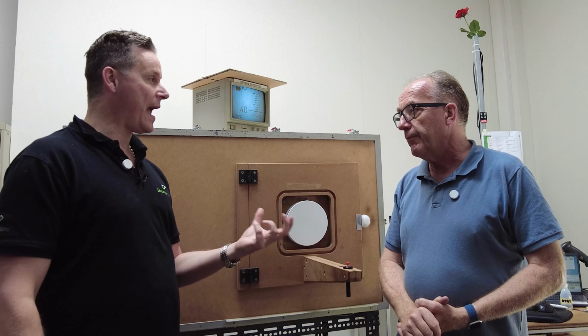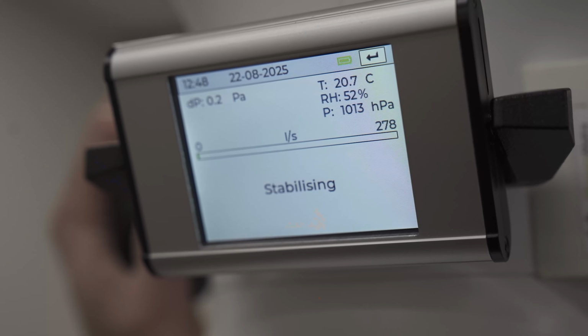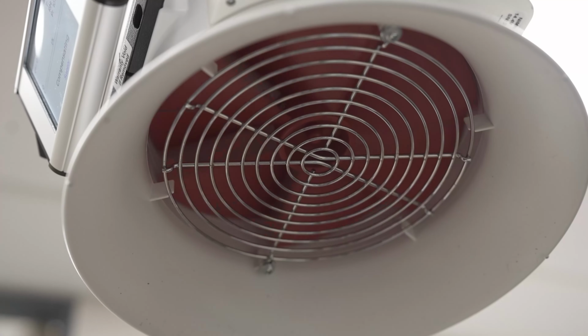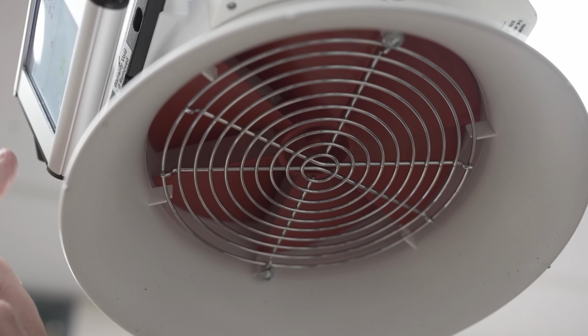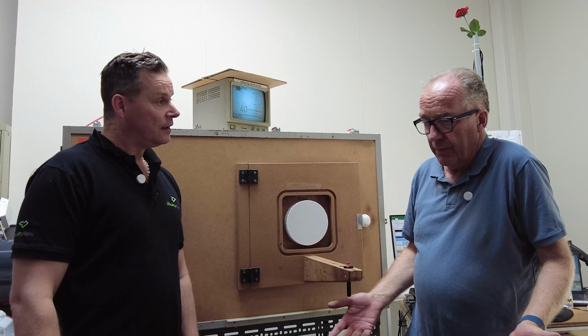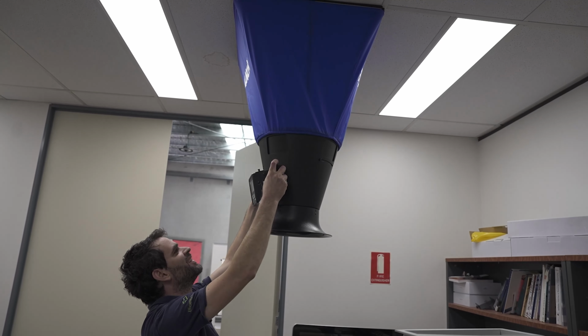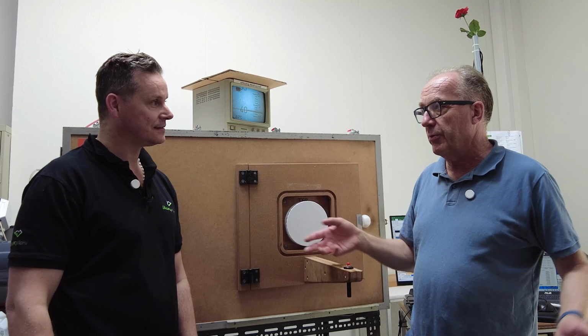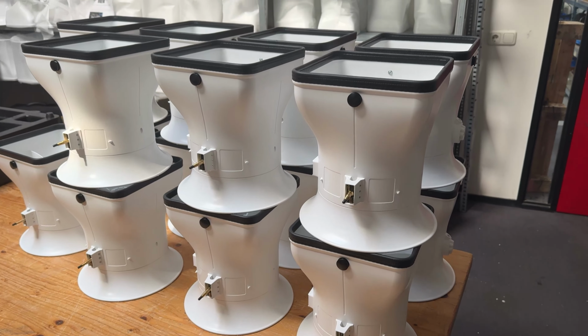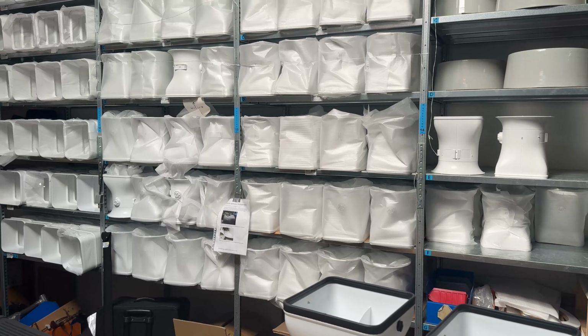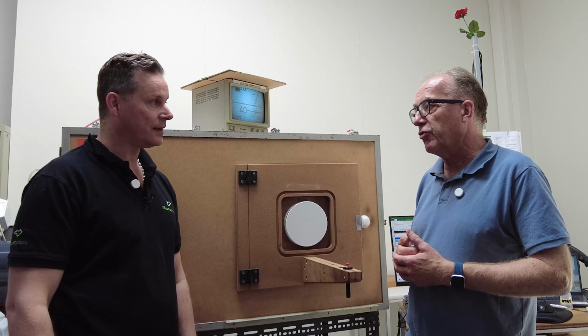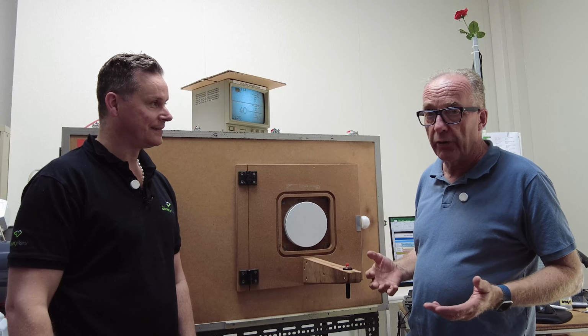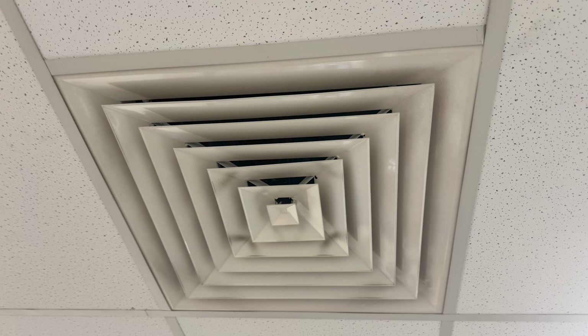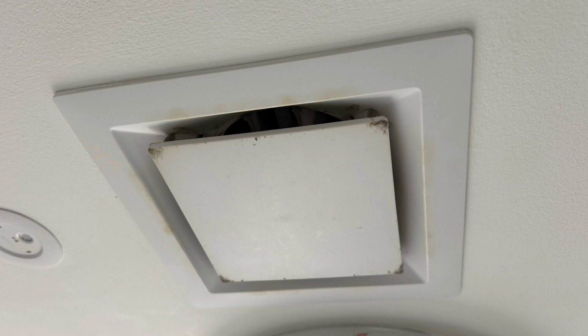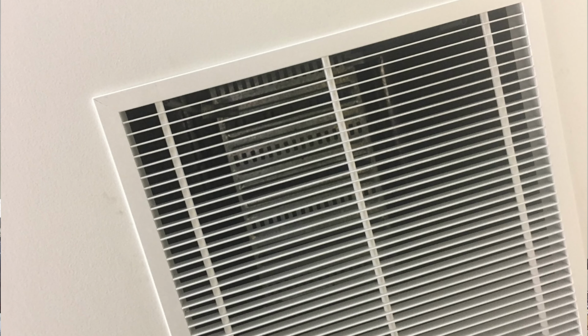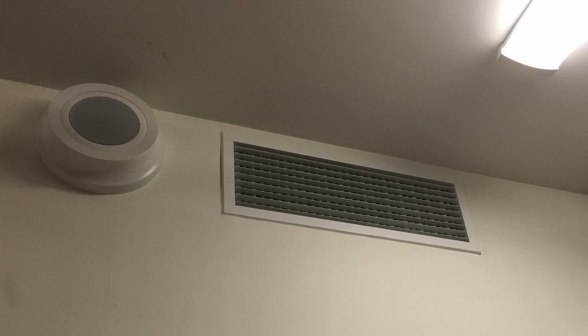So how far out can the flow be when we're using flow hoods? Well, let's assume that you have a properly calibrated flow hood, and then the word properly, of course, you have to define a little bit. It is calibrated on a certain system, and every system is different. So if you match the system on which the flow hood is calibrated, it will be within specs for sure. But that's almost impossible because there are so many grills around, and so many different resistances and systems around, that a standard flow hood can easily be off by 20% or more, depending on the flow pattern.